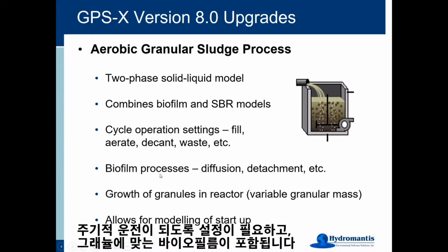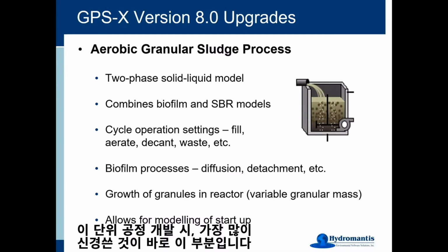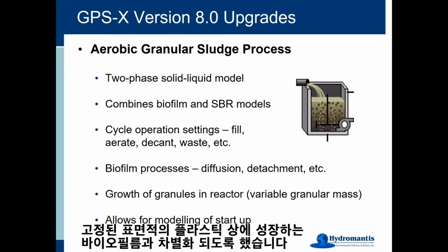As you'll see, it has a full biofilm model, but it's been modified to work for granular sludge as opposed to biofilm growing on a fixed surface area media. That's one of the aspects where we focused quite a lot on the development: granules grow differently than biofilm on a piece of plastic that has a fixed surface area.